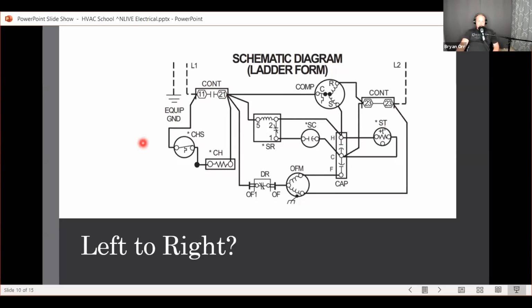Well, that's what this crankcase heater uses, because now it acts as the path in between the two sides. So in actuality, when this contact is open, and this is obviously still closed because that's just a shunt, and again, I'm drawing it left to right, which is silly, because it's not DC, it's going both directions, it's going to come through here, go through the switch, come through here, and then travel through the compressor. It's going to go through the contactor and then back the other side. So this run winding is going to take the brunt of that.